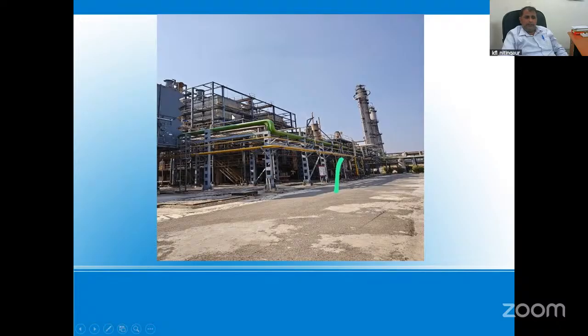All the steam is transferred to the other plants through a pipeline. Since the pressure and temperature are very high, 515 degrees Celsius at 115 kg per cm square, it is very important to select the piping material carefully. As per IBR regulation, welding joints of the pipe should be crack free and pinhole free. Hence, maintenance of the boiler is very difficult.